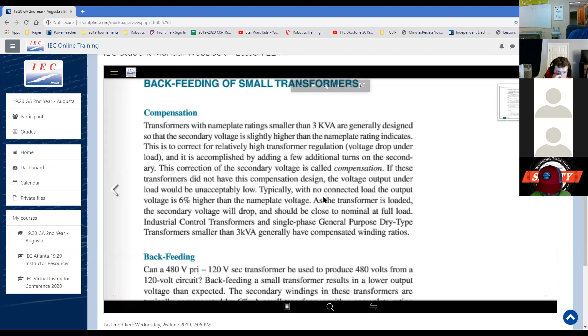So can a 480 volt primary to 120 volt secondary transformer be used to produce 480 volts from a 120 volt circuit? It's called backfeeding. I showed y'all this earlier. This is a pad mount right here. This is a pole mount, just like you'd have on your service pole. You got two 120s and a neutral leg. You got 7200 or 14.4 or whatever it is running through. It just passes through here. Transformers down at the bottom. On that one, the transformers down at the bottom as well. That one is 7200 going in, and two 120 legs and a neutral going out.